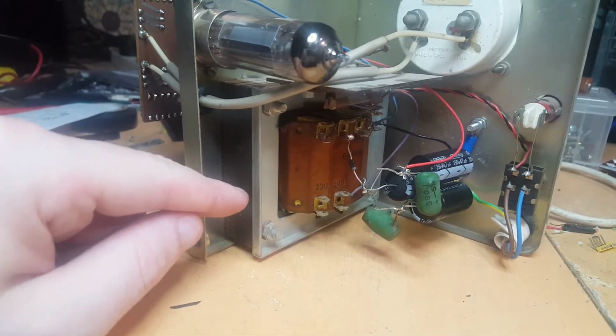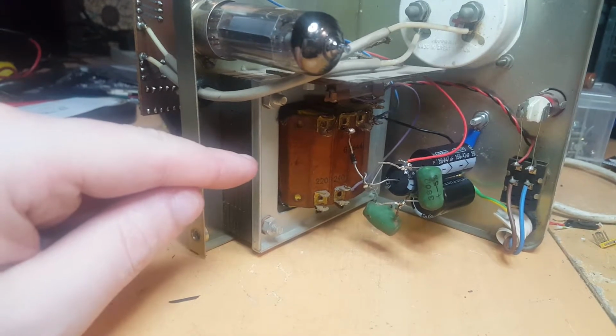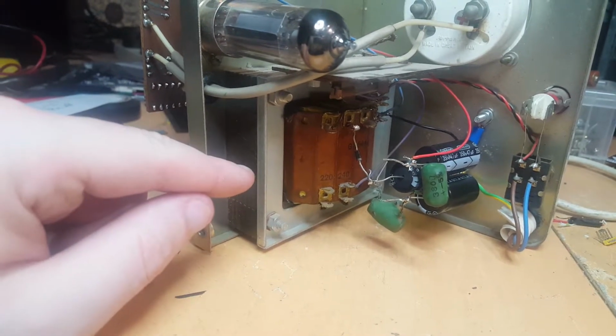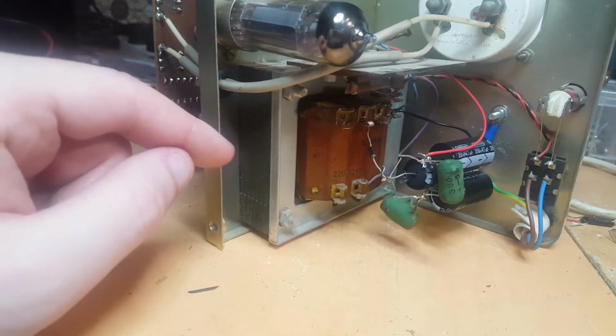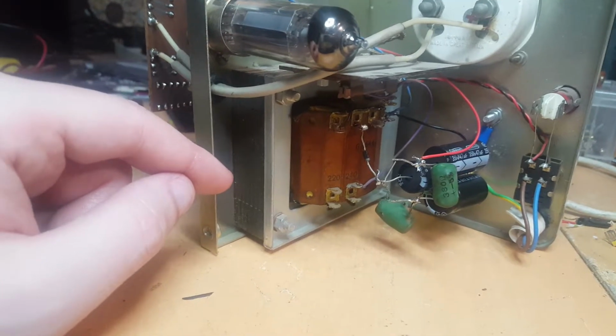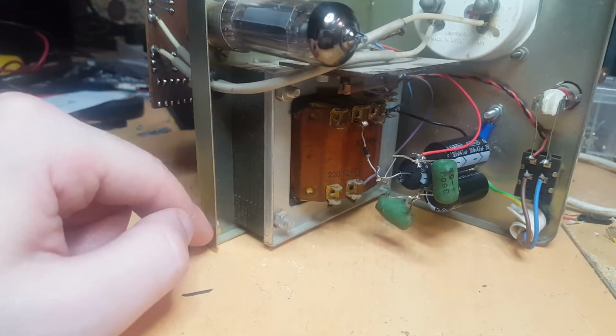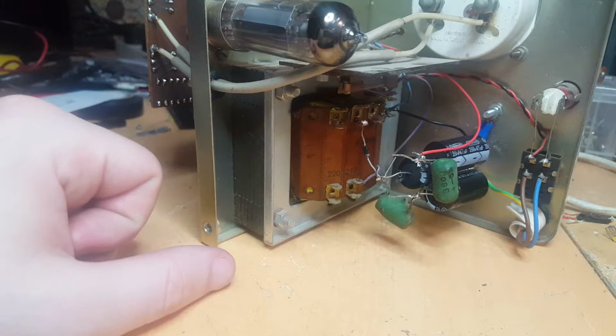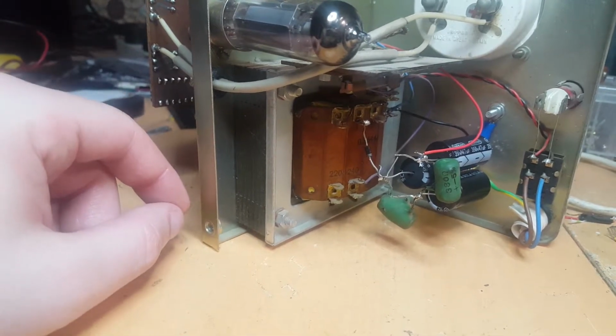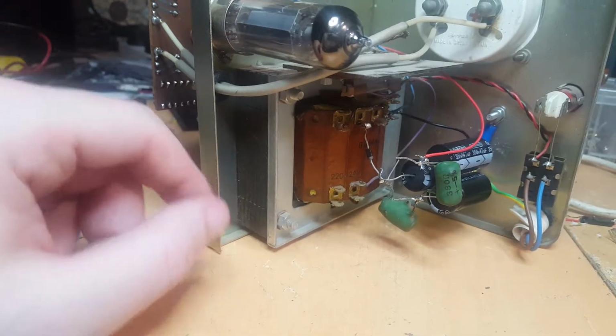Speaking of which, the insulation is good. I have checked it - 15 mega ohms, as high as 20 mega ohms is as high as my meter will read, and it's still reading nothing interwinding. So there's good insulation integrity. All the windings are intact.